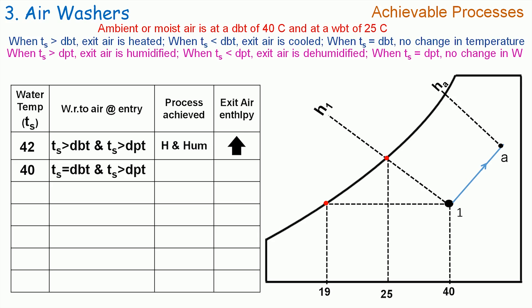Let us now reduce TS to 40°C. Here TS is equal to dry bulb temperature, hence no change in temperature of the air. And TS is greater than dew point temperature, hence air is humidified. Therefore, the achievable process by the air washer is humidification alone. If we plot it on the psychrometric chart, then process 1 to a will be representing it. The enthalpy Ha is greater than H1, hence exit air enthalpy increases.